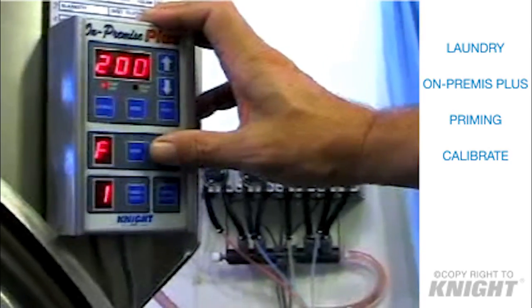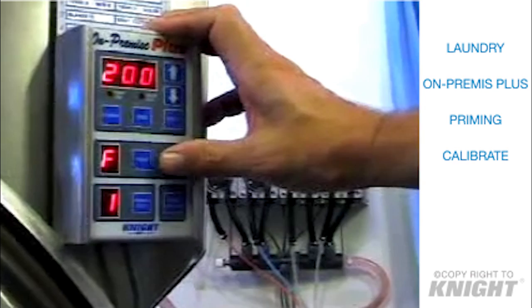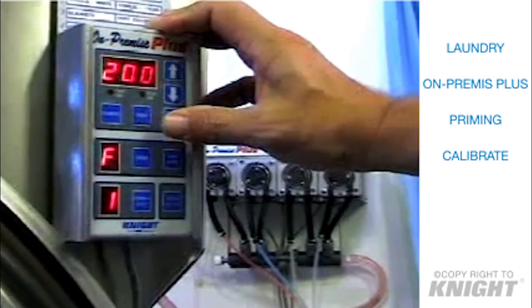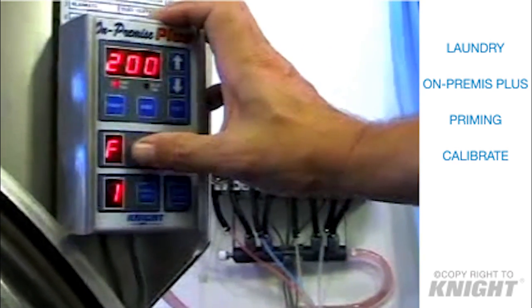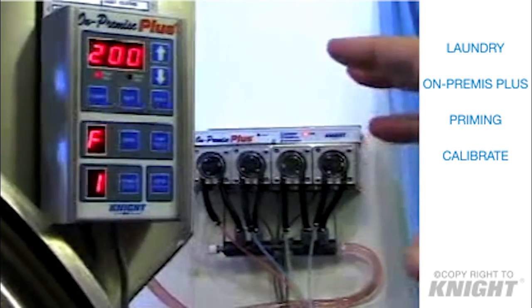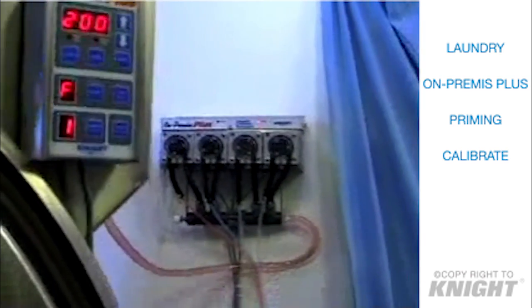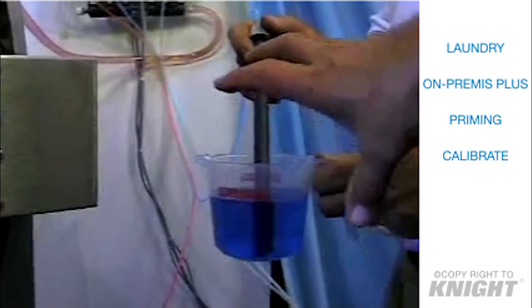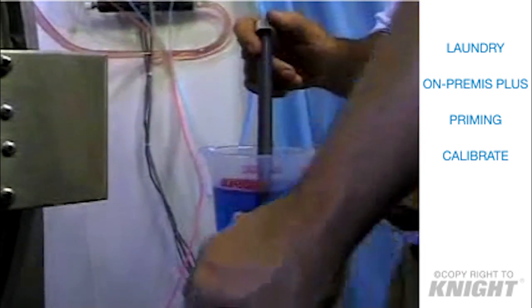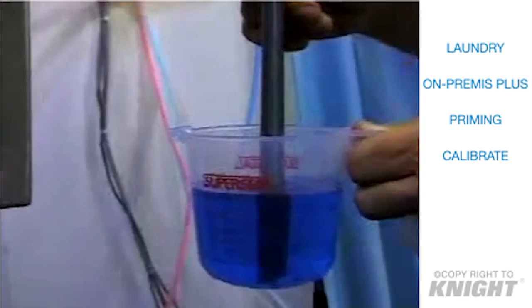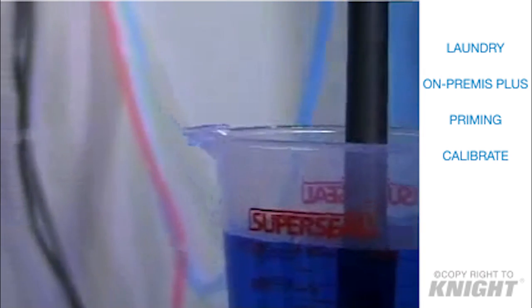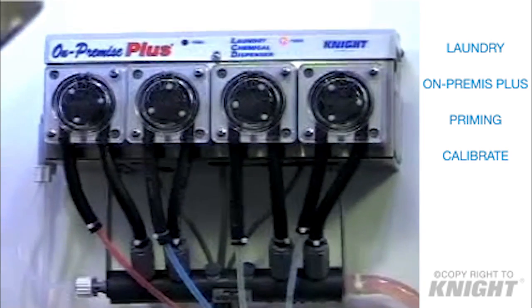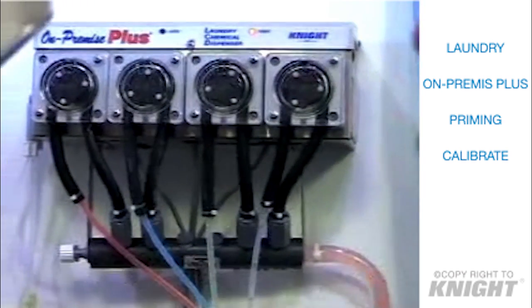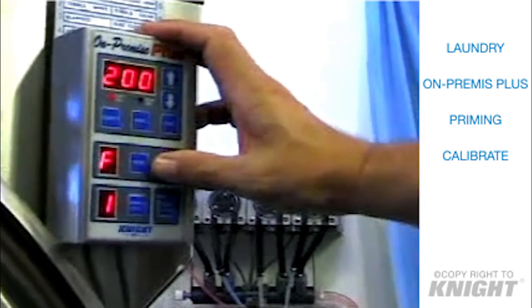Okay, the second method for calibration is automatic calibrate. Start by gaining access to the control. Select flush, because we're going to run the same process we ran a moment ago. We're going to draw from a supply source here. We're going to pump some measured amount. First, make sure you know what your level is. We're going to run flush, and we're going to run our pump number 2 at the same time, and in that way we account for water pressure variations, back pressure through the check valve, viscosity, and distance all at one time. So go ahead and start flush first.